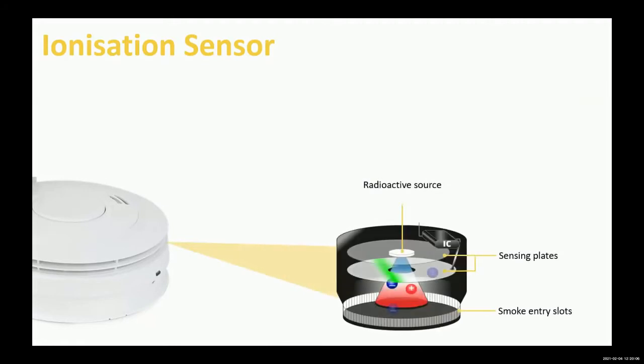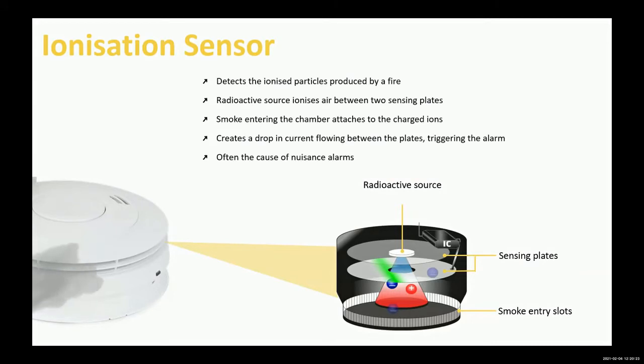If you look at ionization sensors, again, as I said, they're smoke alarms, but they work totally differently. We have a radioactive source within the chamber itself. It's americium-241 is what we use. And we have two sensing plates and the smoke entry slots at the very bottom of the chamber itself. What happens here is that it detects the ionized particles produced by a fire. Now, that's fine if it's a fire situation, but the biggest problem with ionization detectors is that you get ionized air from ovens, from grills, from toasters. It's the same ionized air that's produced by those appliances. So if you have an ionization detector near a kitchen area, you're going to get false alarms.